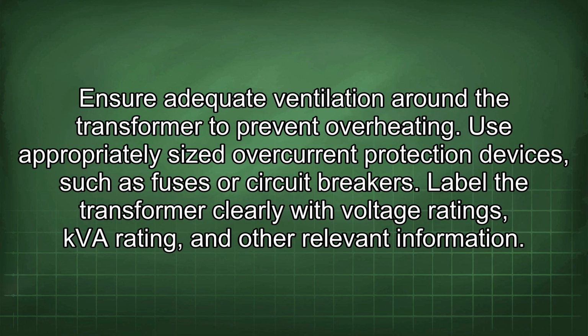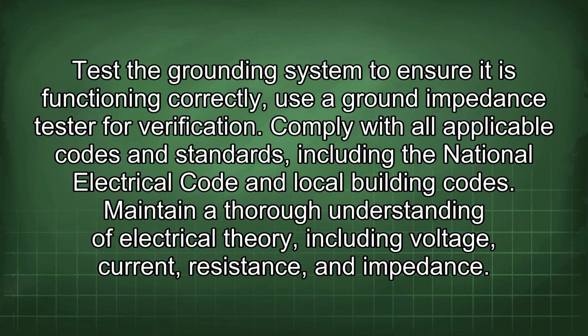Ensure adequate ventilation around the transformer to prevent overheating. Use appropriately sized overcurrent protection devices, such as fuses or circuit breakers. Label the transformer clearly with voltage ratings, kVA rating, and other relevant information. Test the grounding system to ensure it is functioning correctly. Use a ground impedance tester for verification.